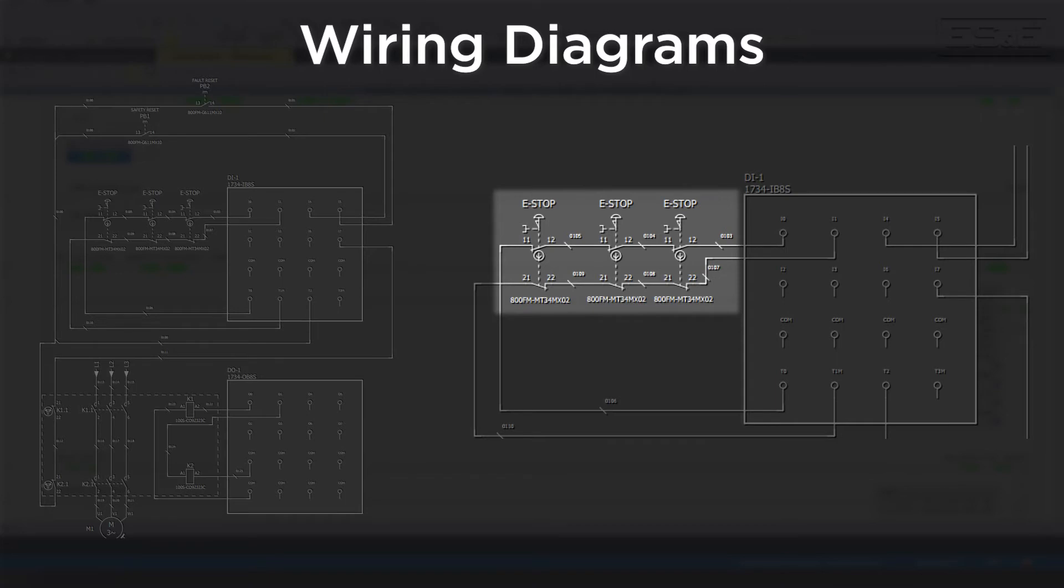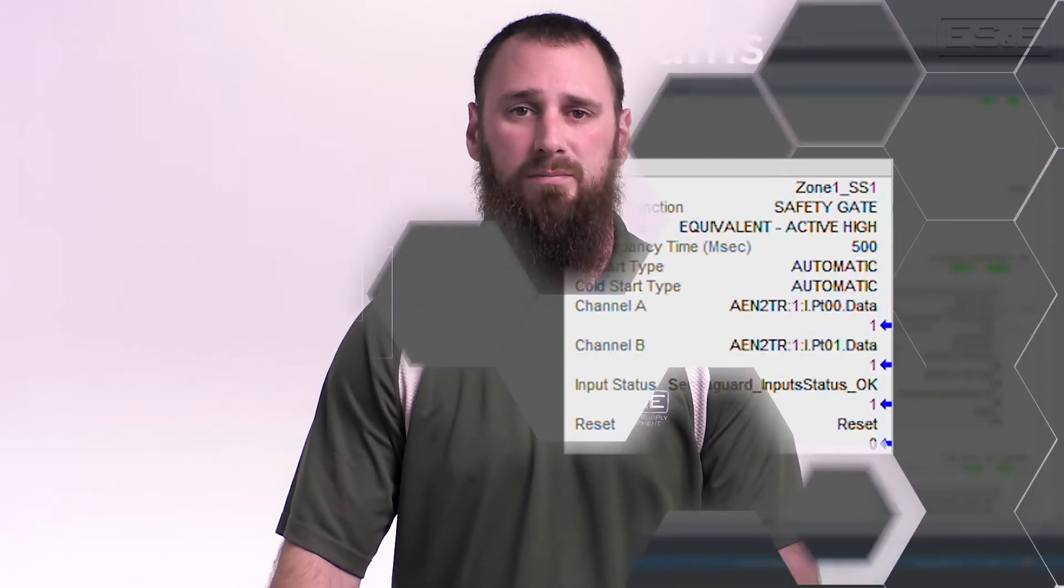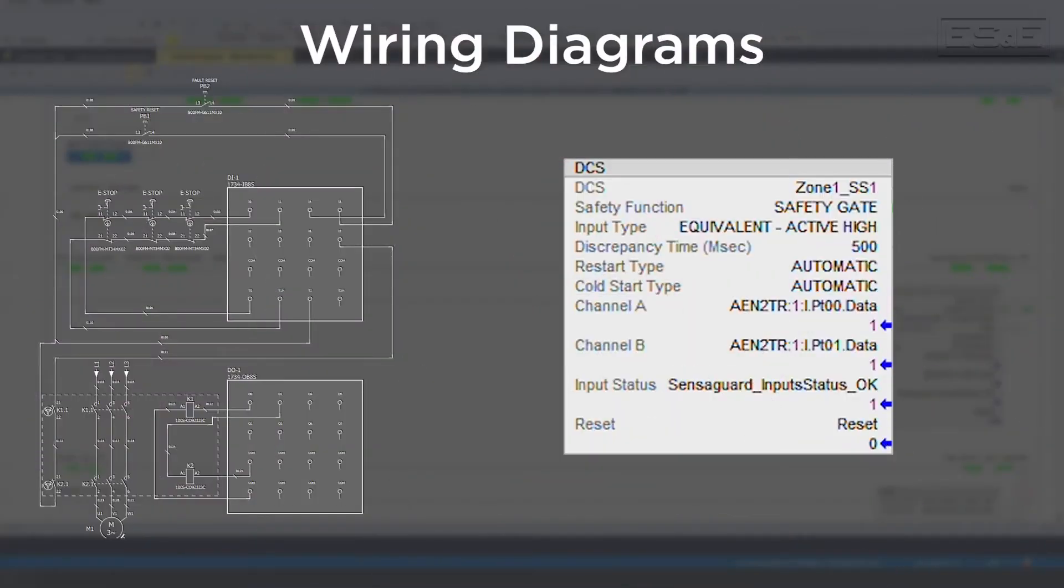Now the same system will look different when wiring a safety controller and safety I/O. This time you will wire from the door switch through the e-stop contacts and directly into input 0 and input 1. One key note is that you can still create a series circuit to save inputs, but you will lose the resolution of which device is causing the issue. Consequently, most systems will wire each device directly back to the controller and add additional DCS instructions to monitor each device individually.